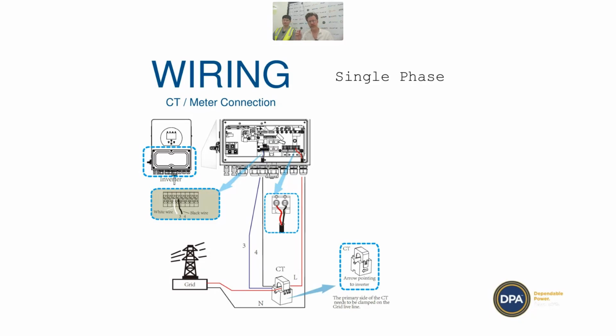It's really easy to get the CT the wrong way around. So I recommend that once everything's working, go put the kettle on, or put some large load on, and check that the direction makes sense with the load you've got, because it's really easy to have it backwards, and it means a bunch of the other functionality won't work properly.